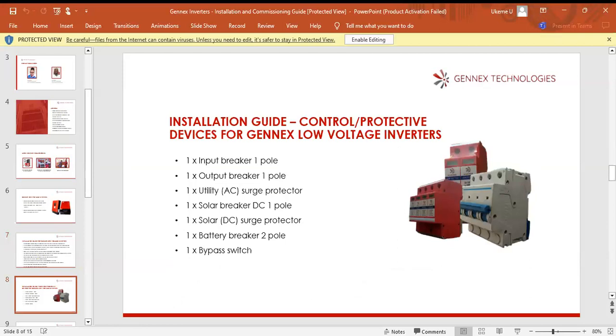So that's the installation guide, control, and protective devices for Gennex low voltage inverters. One input breaker, which is one pole. Most of our breakers for this model of inverter are one pole. So you have one for input, one for output. They are single pole. One utility, which is an AC surge protector. One for the input, then one for solar, depending on how many strings of solar panels you have.